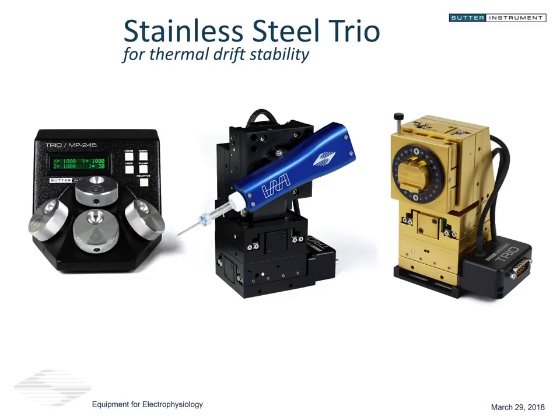So if we've had these set up on flimsy tables at vendor shows and whatnot, where there's a lot of vibrations on the table and on the floor, it's not isolated by an air table. And then we'll have a pipette in the aluminum manipulator and a pipette in the steel manipulator, and you can actually see that that steel manipulator blocks a lot of the vibrations from getting to the pipette. It's almost as if the tables at these trade shows are vibrating around the manipulator itself.